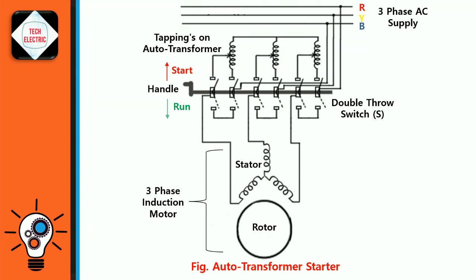When the motor picks up the speed of about 80% of its rated value, the handle H is quickly moved to the run position. Thus, the Auto Transformer is disconnected from the circuit, and the motor is directly connected to the line and achieves its full rated voltage.